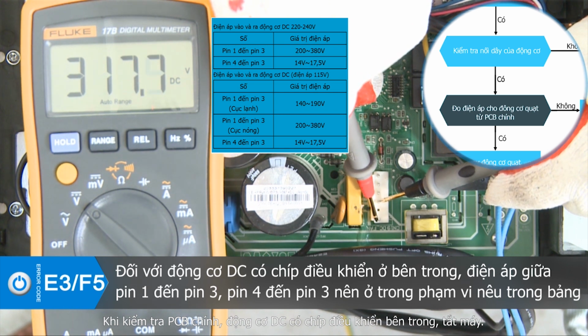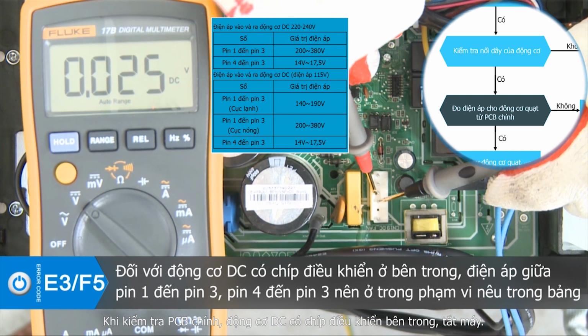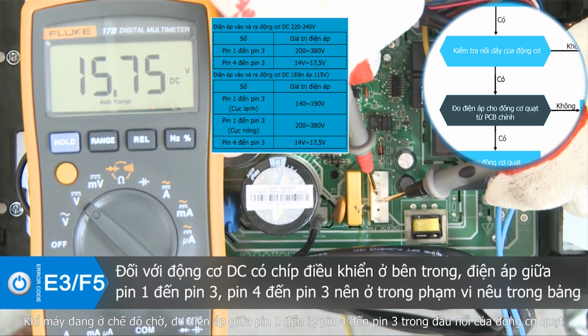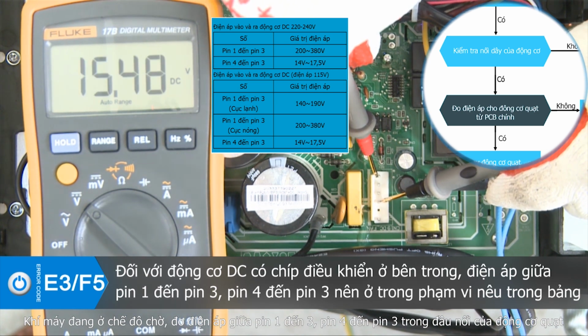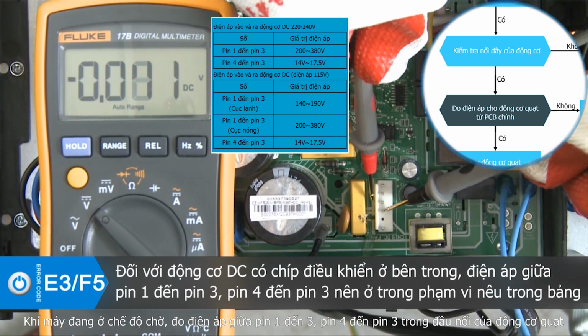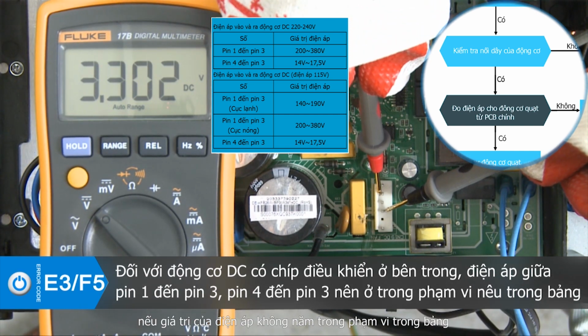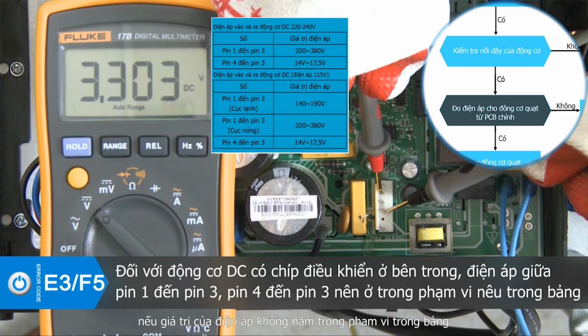Examination for main PCB board. DC motor with control chip in itself. Turn the power on. When the unit is in standby mode, measure the voltage between pin 1 to pin 3, and pin 4 to pin 3 in the fan motor connector.